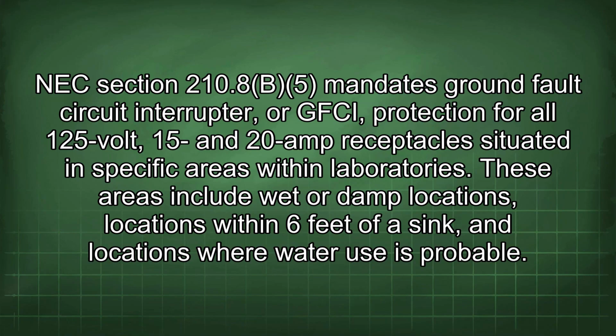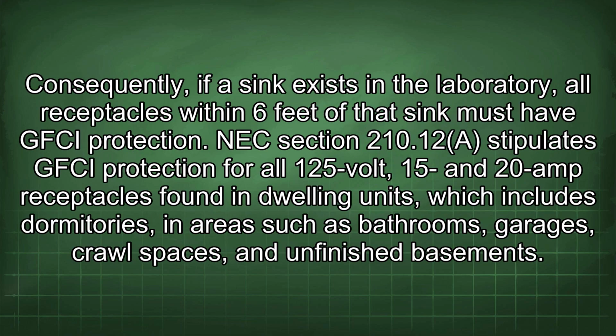NEC Section 210.8(B)(5) mandates ground fault circuit interrupter, or GFCI, protection for all 125 volt, 15 and 20 amp receptacles situated in specific areas within laboratories. These areas include wet or damp locations, locations within 6 feet of a sink, and locations where water use is probable. Consequently, if a sink exists in the laboratory, all receptacles within 6 feet of that sink must have GFCI protection.